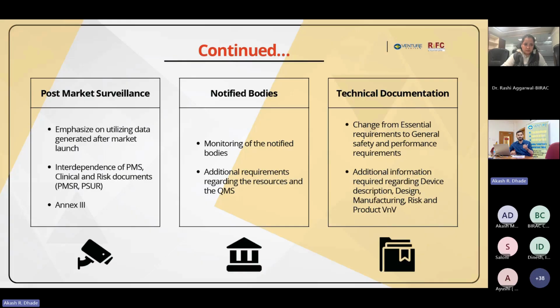Like device description, then accessories section, then labeling and IFU, then general safety and performance requirements, then risk management, clinical evaluation data, post-market surveillance data, and V&V, verification and validation data. These are all the sections that you need to prepare in a summarized format. And that summary is taken based on the documentation specific to risk management, the clinical evaluation report, and V&V data.